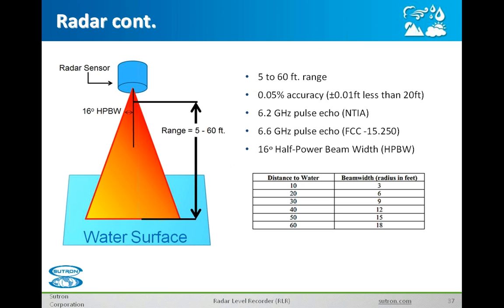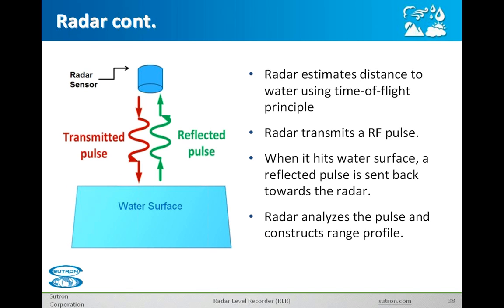Once it knows the stage and the distance to the water, it knows the total distance to the bottom of your channel, and from that point it can track the water level just by tracking changes in the distance to the surface. All radars produce a beam that extends and gets wider the higher up the sensor is mounted. So you need a certain clear distance depending on the height — the radius increases and you need to make sure you have a clear view of the water. It doesn't do well bouncing off rocks or the bank of the stream or channel. The radar sensor emits a pulse and whatever is reflected back is how it gets its reading — bouncing off the water surface is what you want.